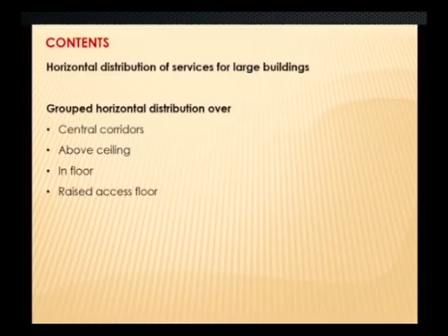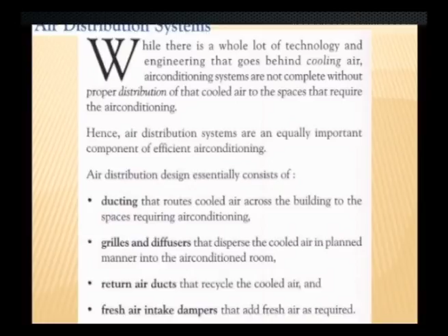While there is a whole lot of technology and engineering that goes behind cooling air, air conditioning systems are not complete without proper distribution of that cooled air to the spaces that require air conditioning. Hence, air distribution systems are an equally important component of efficient air conditioning. They consist of ducting that routes cooled air across the building to the spaces requiring air conditioning, grills and diffusers that disperse the cooled air in a planned manner into the air conditioned room, return air ducts that recycle the cooled air, and fresh air intake dampers that add fresh air as required.